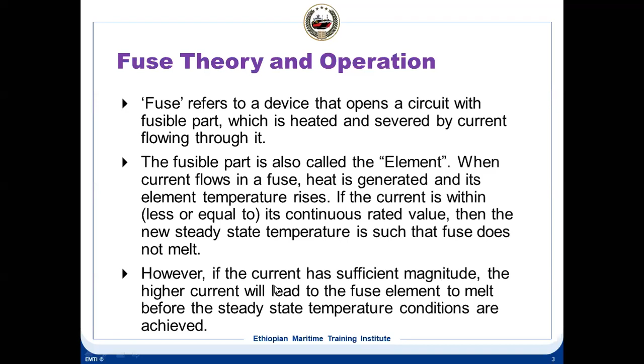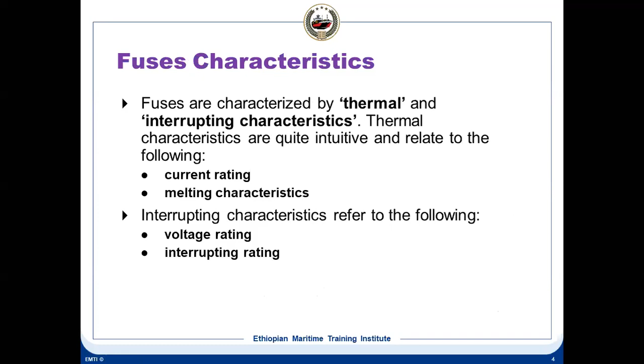Okay, I hope it is clear what this inverse characteristic is. As the magnitude of the current increases, the melting time reduces. So the larger the magnitude of the current, the higher the power absorption in the fuse, and the faster the rise in temperature. So the melting time of the fuse is inversely proportional to the square of the current magnitude. So that is called inverse characteristic or inverse melting characteristic. The fuses are characterized by two things: thermal and voltage. Thermal means current ratings and melting characteristic. The other one is the voltage ratings and interrupting characteristic.